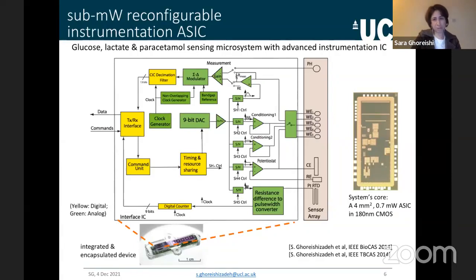I mean, that tree of electrochemical techniques that we didn't go through, for different types of measurements, we need different voltages to be applied to the sensor, and for the sensor to be kept at those voltages for some time before we can actually start reading from the sensor. So there were various elements here. It was the most advanced instrumentation circuit at the time, because not only could it read out the sensor, but it could keep them prepared for the measurement. And all the signals, all the waveforms were produced based on a single digital to analog converter, followed by different sample and hold circuits that were controlled internally through some digital control units.